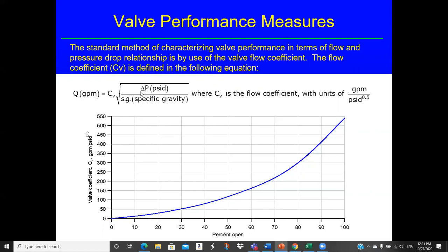This is typical in the US. The delta P is in PSI. D stands for differential. And of course, I think we've talked about specific gravity. That's the density of your fluid that you're pumping or is going across the valve, divided by the density of standard water. Okay, and so if you just look at this, that requires that the units on CV be GPM divided by PSI differential to the 1/2. And of course, specific gravity is dimensionless.